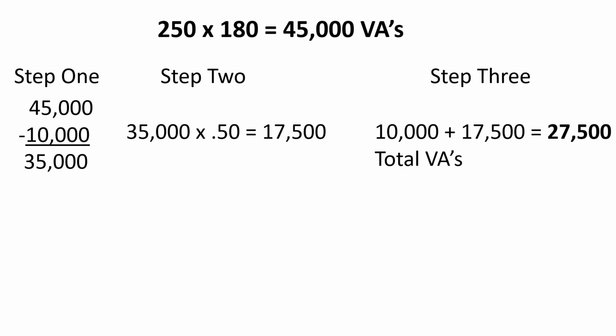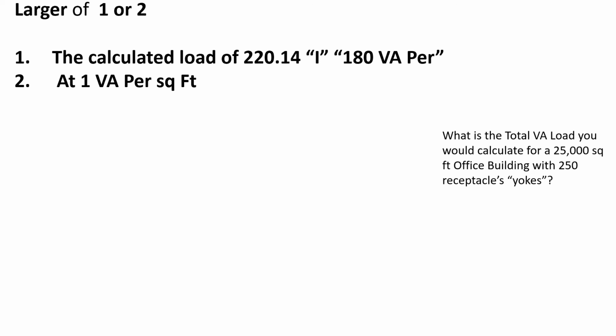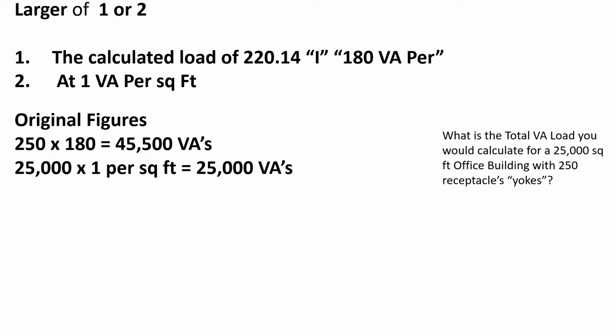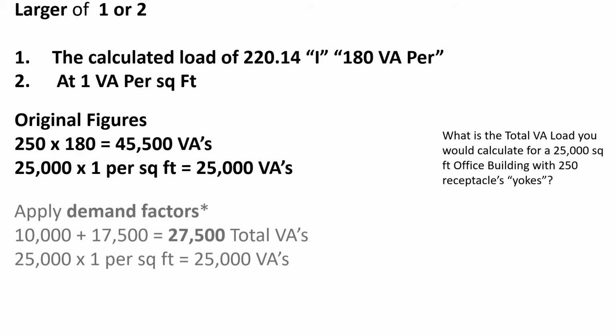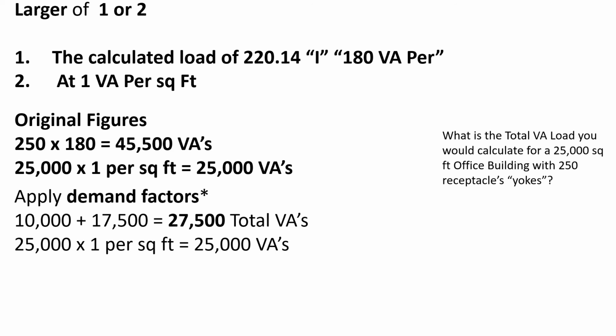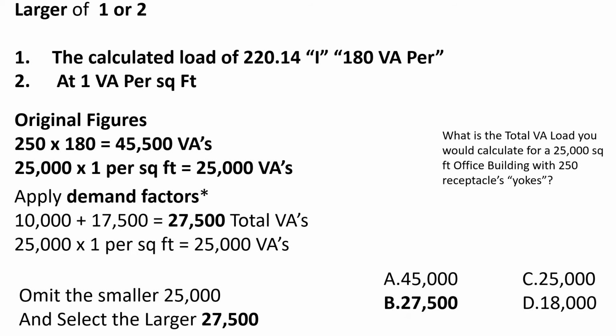Now in step 3, all we do is take the 10,000 that we set to the side and add it back to the reduced load with the demand factor, and that is going to give us the new total VAs. In this case, it's 27,500 VAs. Now we must select the larger of 1 or 2. These were our original figures, then we applied the demand factors. Now we must omit the smaller and select the larger, and in this case, it's going to be B, 27,500.